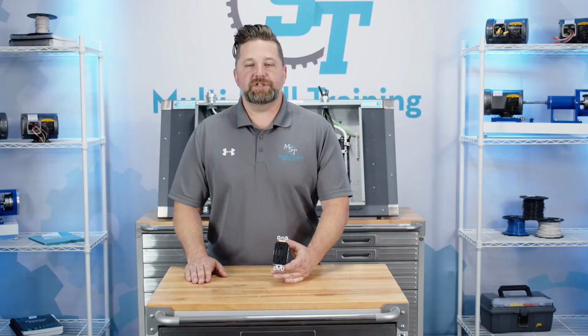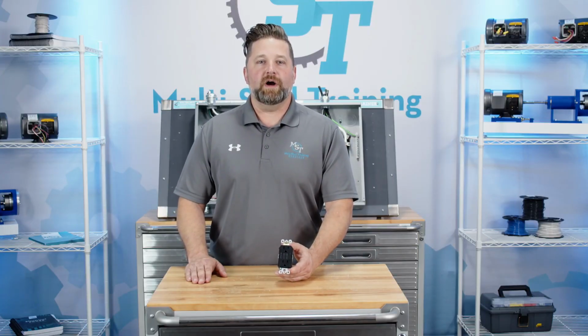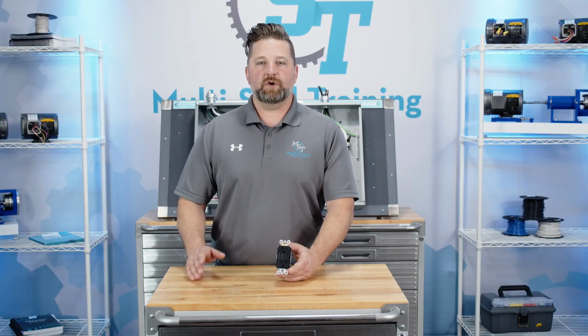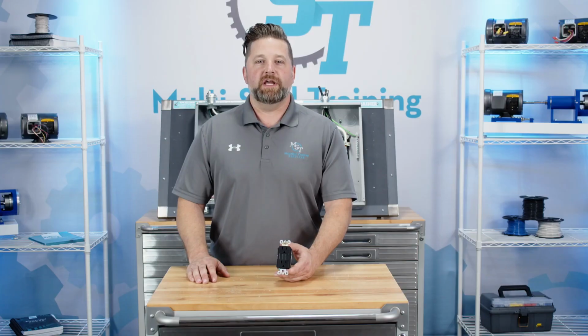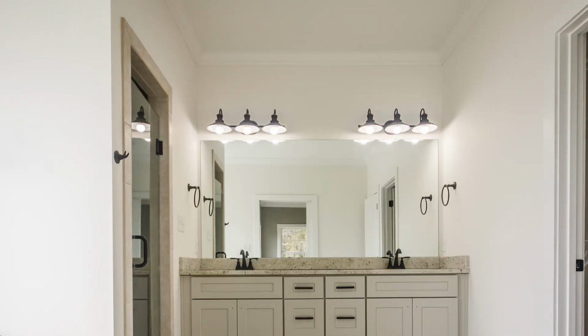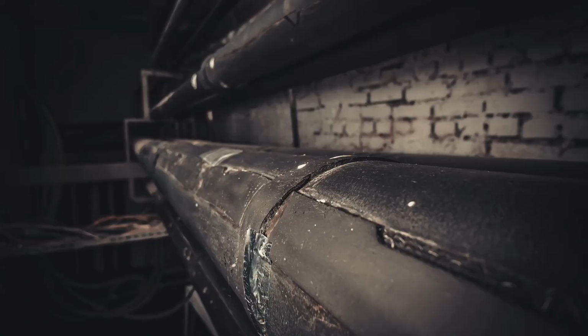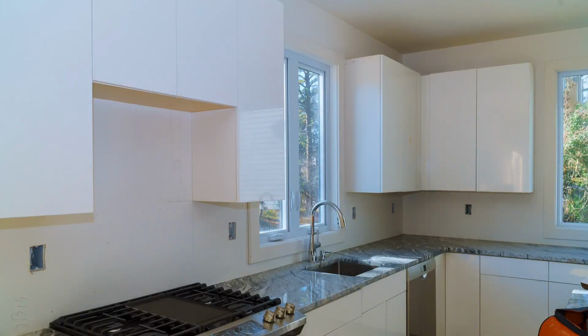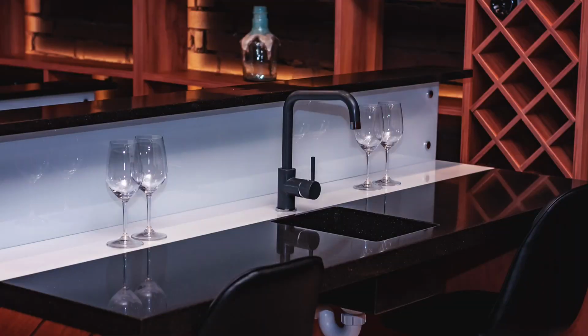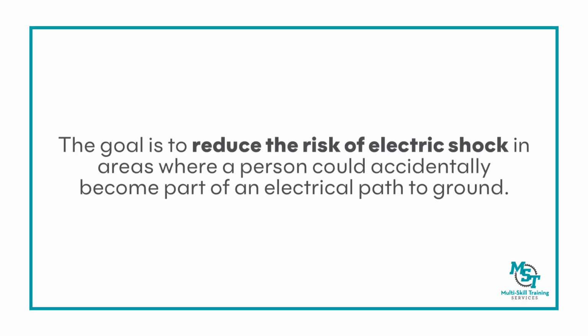GFCIs provide enhanced protection compared to standard outlets or isolated ground outlets. Electrical codes require GFCI protection in locations where moisture is common or where equipment is exposed to water. These locations include bathrooms, garages, unfinished basements, crawl spaces, kitchen countertops, outdoor areas, and within 6 feet of wet bar sinks. The goal is to reduce the risk of electric shock in areas where a person could accidentally become part of an electrical path to ground.